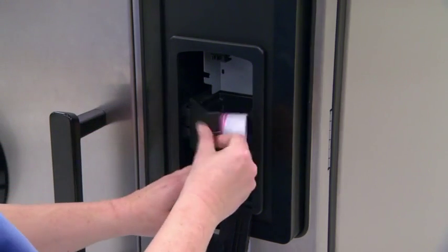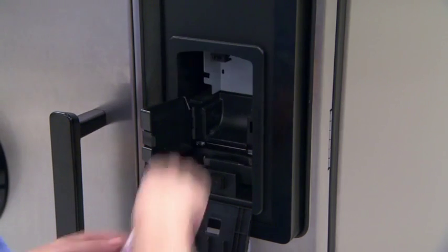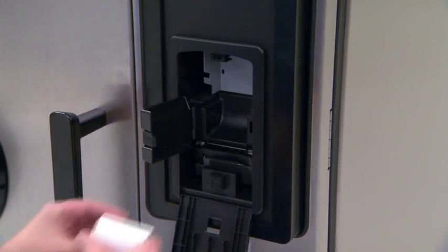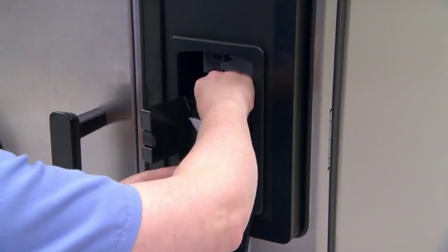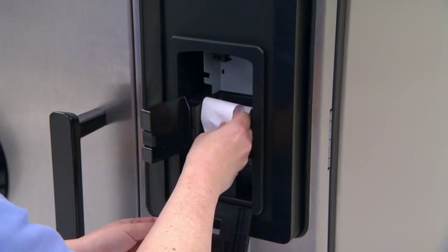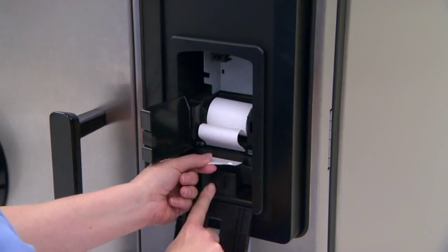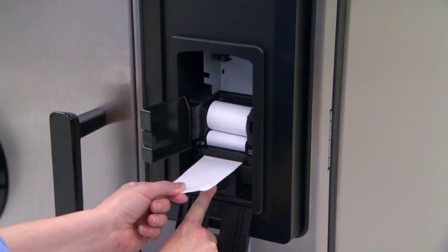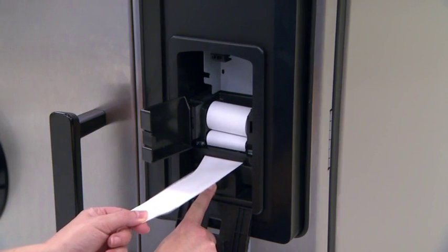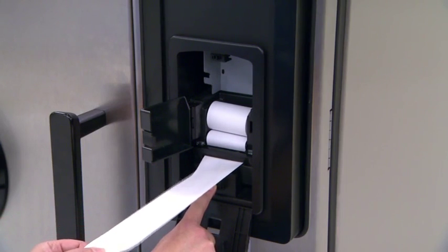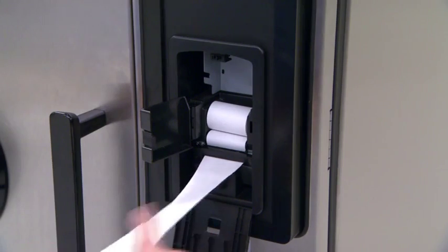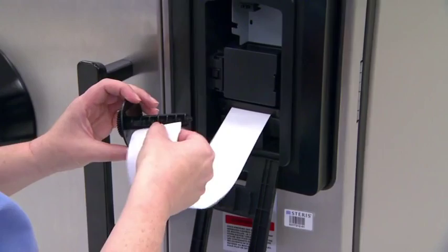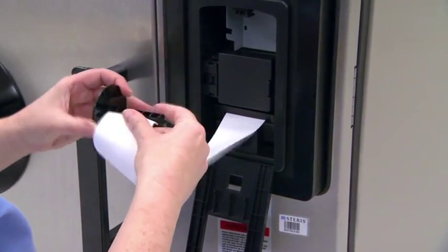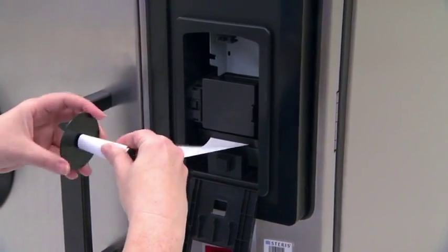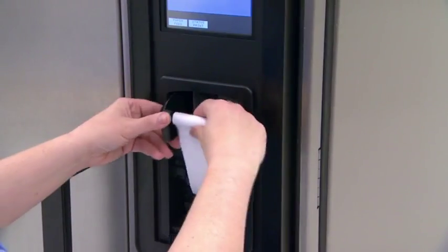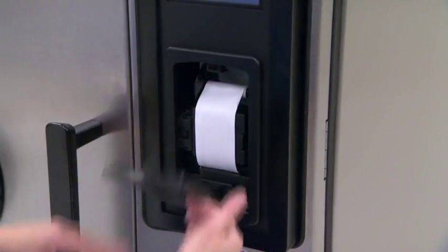Open the access door and remove the old paper roll, gently pulling any remaining tape out of the printer roll mechanism. Insert the new paper roll. Insert the end of the paper into the printer roller mechanism just behind the ink cartridge. Press the paper feed button on the printer until the paper advances through the printer mechanism and ink cartridge, exiting through the front. Continue pressing the paper feed button until about 18 inches of paper hangs out of the printer. Insert the end of the paper into the slot on the take-up spool. Coil the paper around the take-up spool until it's secure. Reinstall the take-up spool in the bracket and manually roll up the slack paper. Close the printer door.